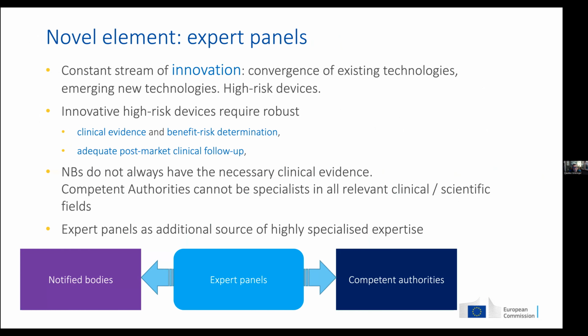So I wanted to talk a little bit about expert panels in medical devices, and conformity assessment with standards also. We have a lot of innovation in that field. A lot of the devices that are very innovative are, of course, high-risk devices. And you need there good clinical evidence and a robust risk-benefit determination. And of course, what's very important, adequate post-market clinical follow-up. What I wanted to emphasize is that the legislation in Europe realized that the notified bodies do not always have the necessary clinical expertise, and also the competent authorities cannot be specialists in all relevant clinical and scientific fields.